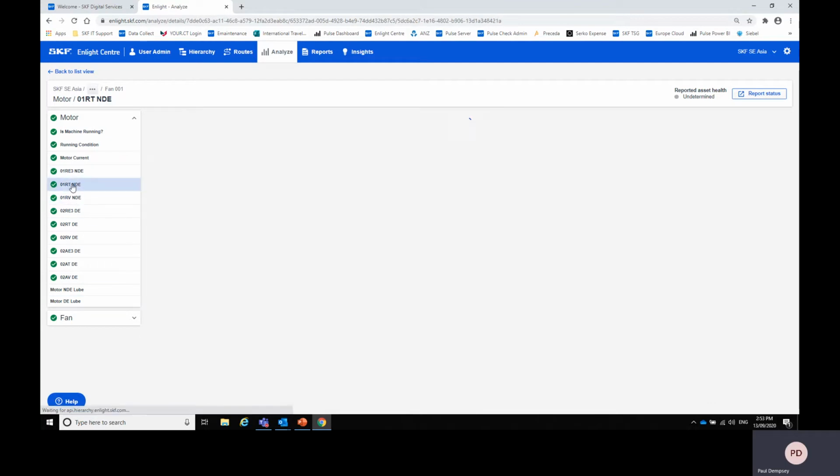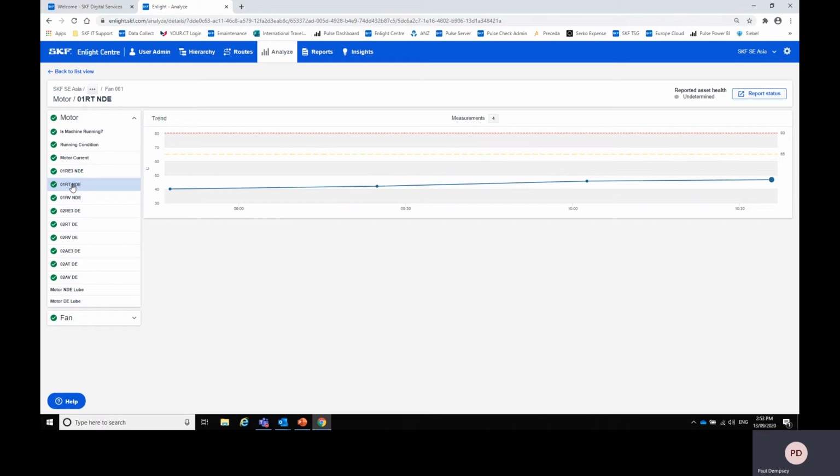Also below that here we have a temperature point taken with the Quick Collect sensor, and you can see here the temperature, although it has been trending up a little, is still below alarm levels, and a temperature of 46 degrees would most likely not be a problem. So this is the basic way you access the data.